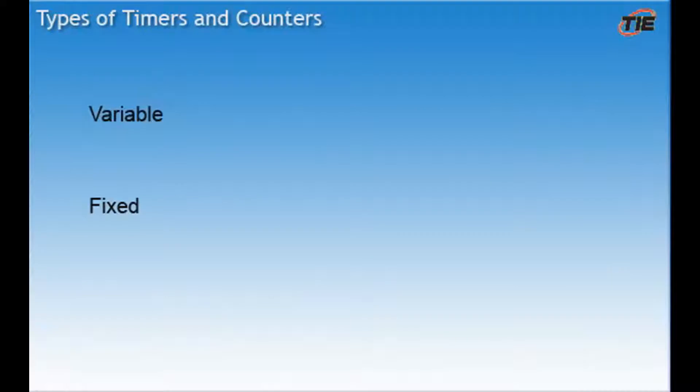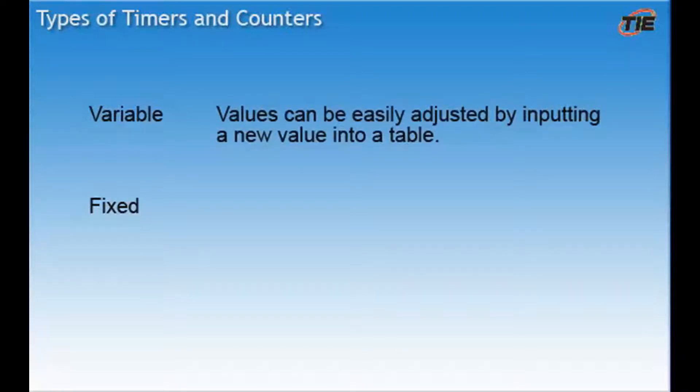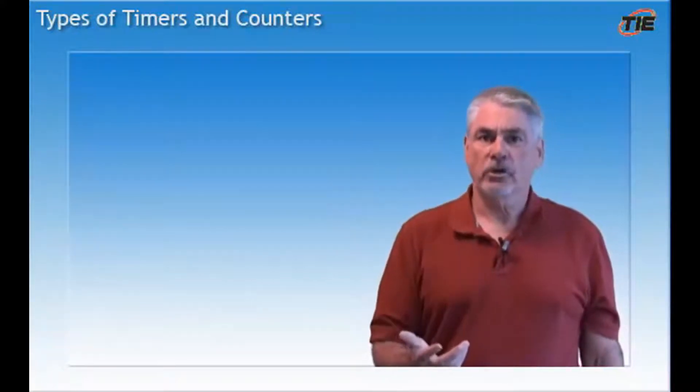There are basically two types of timers and counters used on the FANUC controls. These are variable and fixed. Variable means that you can easily adjust the values. This is done by going to the timer or counter screens and inputting a new value. Fixed means that the timer or counter value is hard-coded into the ladder. In order to adjust these you will need to edit the ladder.